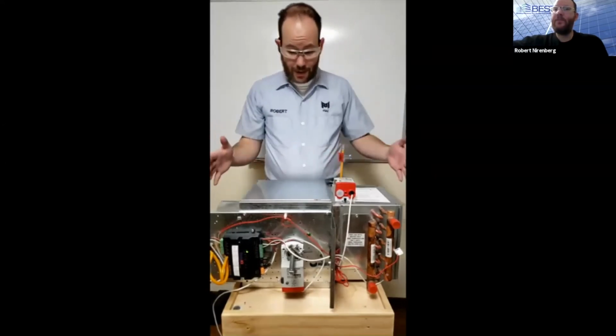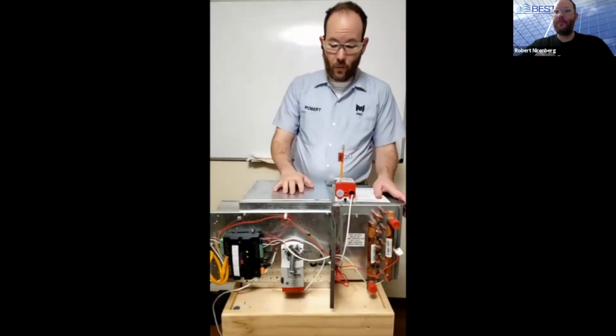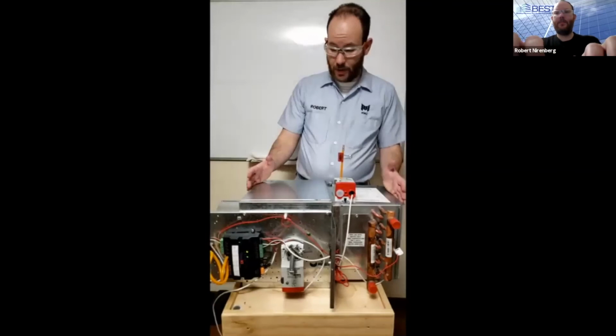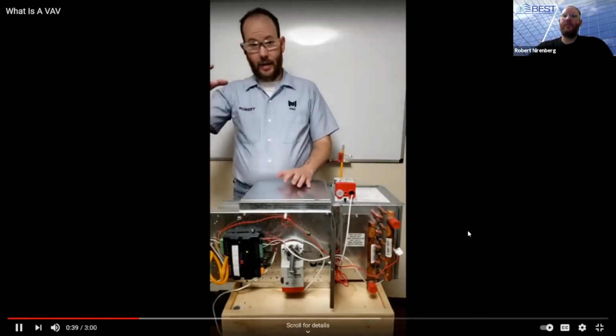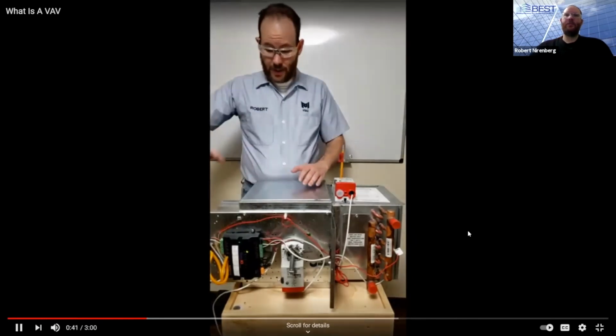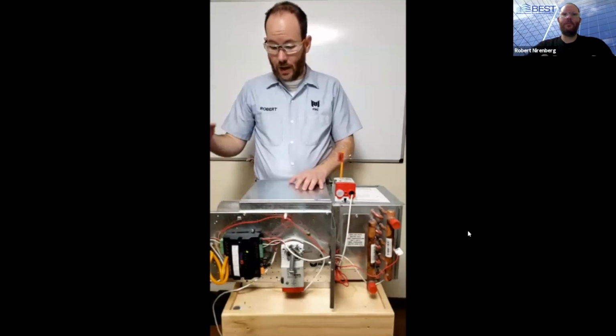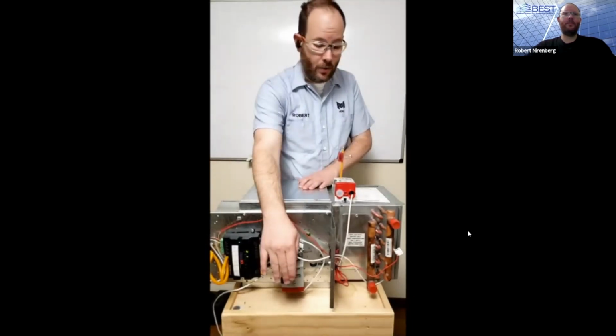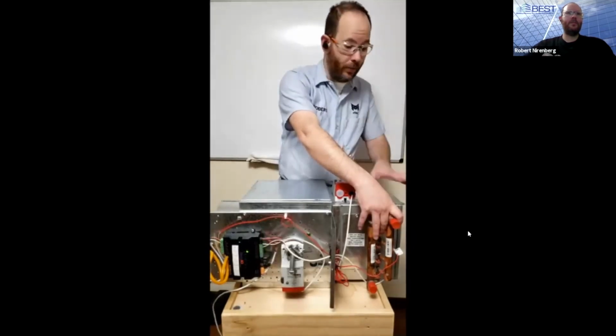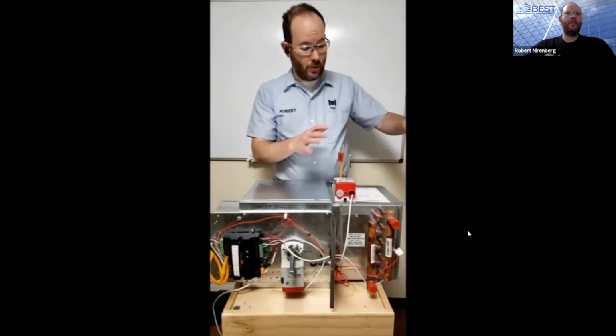So this is an example of a VAV box, okay? VAV stands for variable air volume. What happens with this system, this is an end use, end zone device. So we are providing primary air that comes into the box here on this end, is controlled by a damper internally and passes over, in this case, a reheat coil as the final stage before it transitions out to the diffusers, okay?